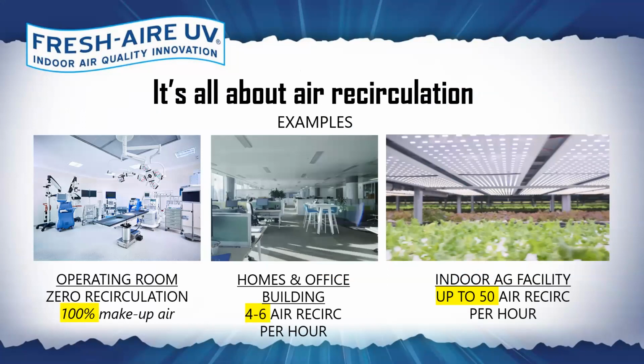Now, if we're contacted by a hospital and there's an operating room, for example, chances are they're bringing in 100% makeup air. There's no recirculation. And if you recall back to my earlier example, when we were talking about the fundamentals of UV technology, we're talking about sunburns, how one sunburn is not going to be an issue for anybody, but continually abusing the sun with enough sunburns have the accumulation of UV to the point of mutation, which presents itself as skin cancer. Well, for a hospital with 100% makeup air, there's no second, third, fourth sunburn.